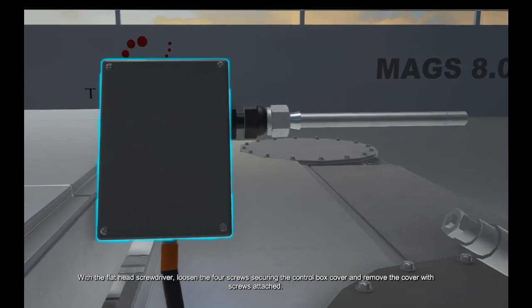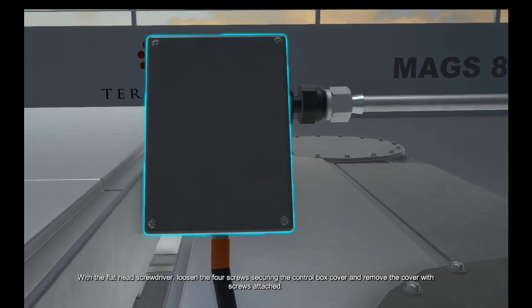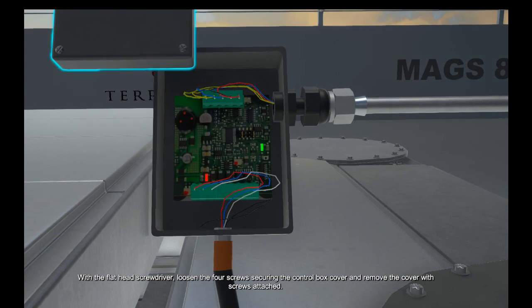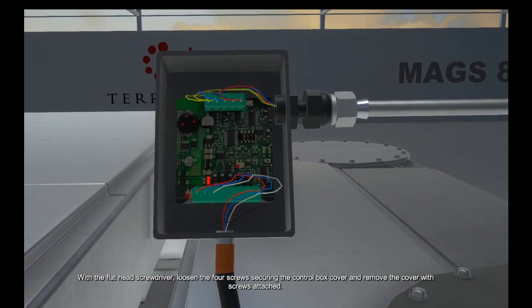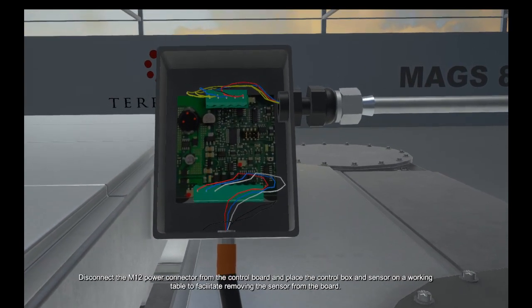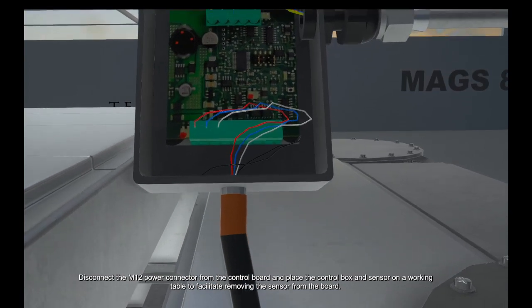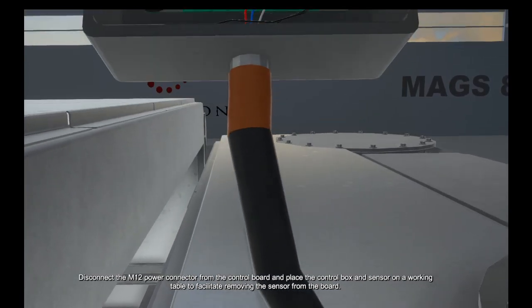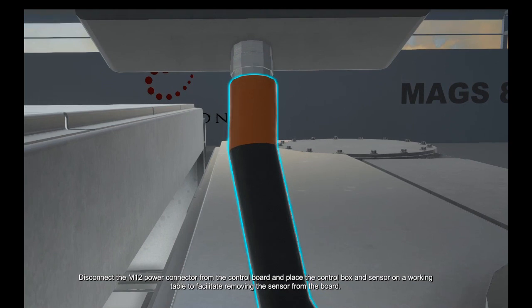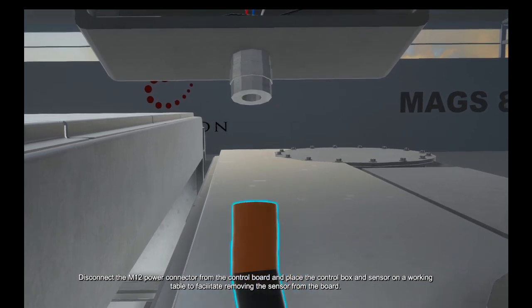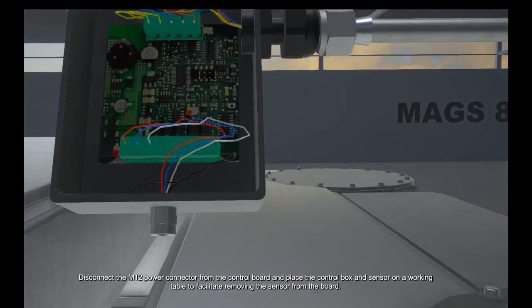With the flathead screwdriver, loosen the 4 screws securing the control box cover and remove the cover with screws attached. Disconnect the M12 power connector from the control board and place the control box and sensor on a working table to facilitate removing the sensor from the board.